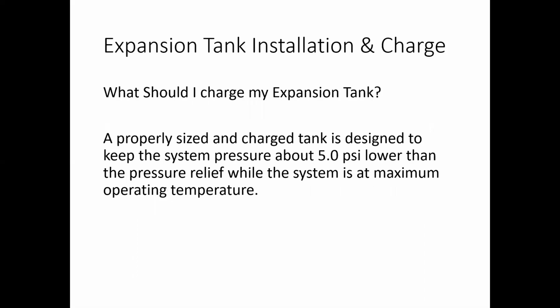The other question that we constantly see is, what should I charge my expansion tank to? A properly sized and charged expansion tank should keep the system pressure about 5 psi lower than the pressure relief valve at the maximum operating temperature. There are some formulas to it, but you can contact Wallace Ennis, we can come in and sit down to talk about how to accurately size that expansion tank.